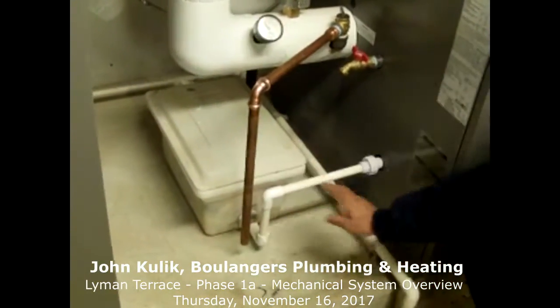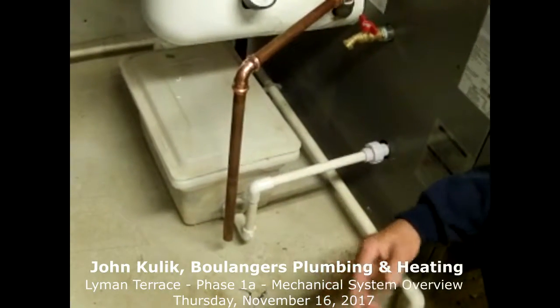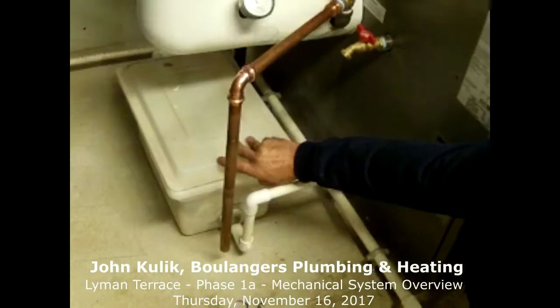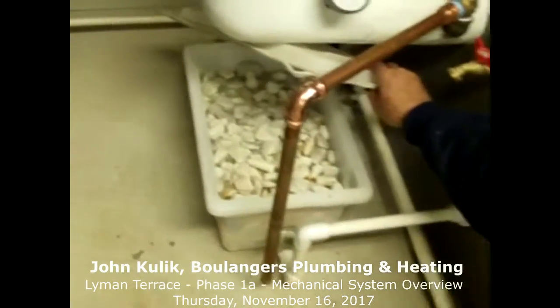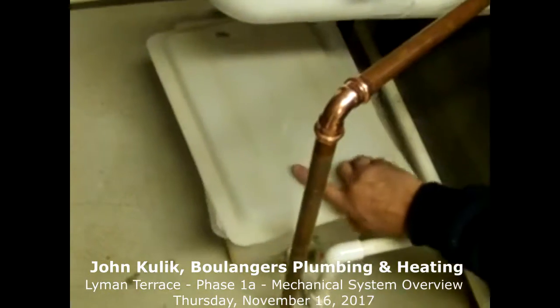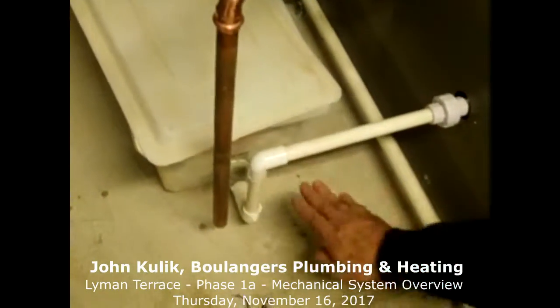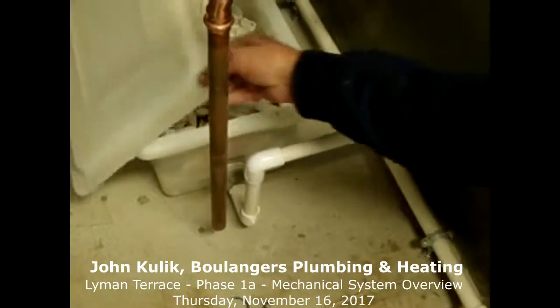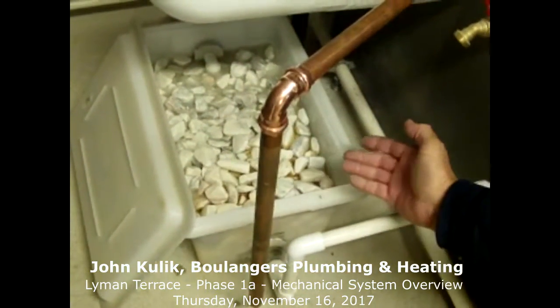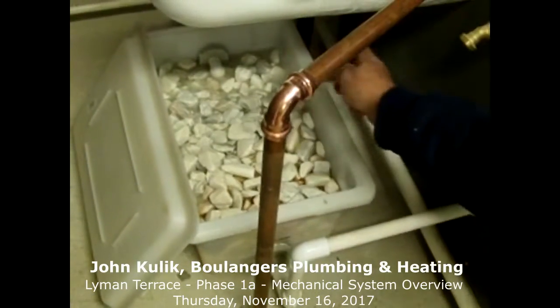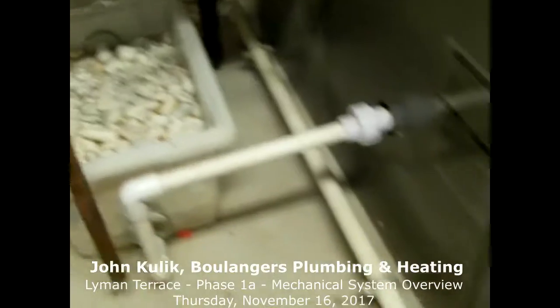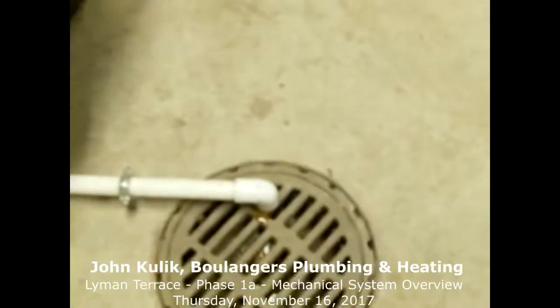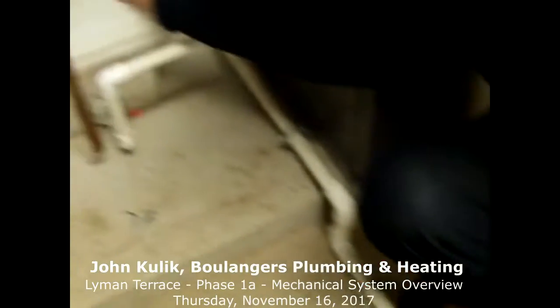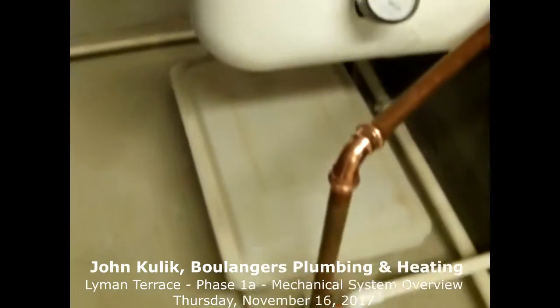That is the drain system here. This is the neutralizing box. What happens here is the water that comes out of the boiler during combustion is acidic. It then gets neutralized through these marble chips. That then does gravity through. It fills up from the bottom so that it has as much time as possible to be in contact with the neutralizing stones. It then relieves itself out as an overflow and down through the drain, and that is treated water now. That protects the drain system. Okay. So this neutralizing... That will be serviced yearly. Yearly. Good. Correct.